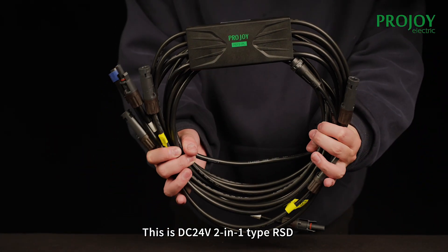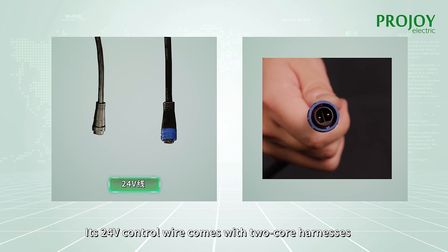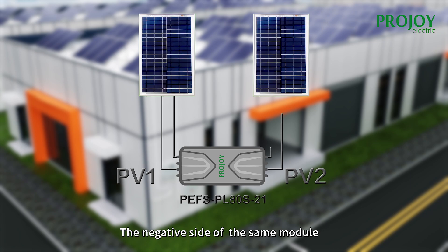This is the DC 24 volts 2-in-1 type RSD. Its 24 volts control wire comes with 2-core harnesses. For the PL80S type, when connecting its PV port to the module wires, use the positive side of PV1 wire to connect the positive side of the module, and the PV1 negative connects the negative side of the same module.